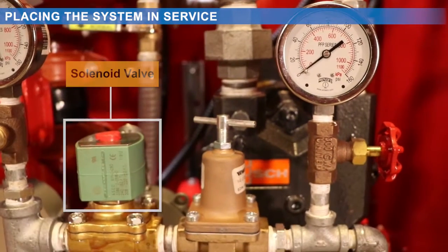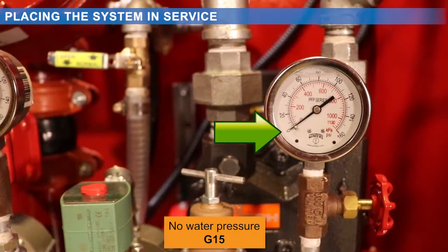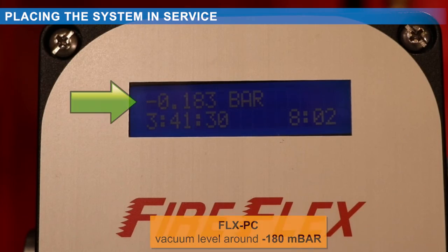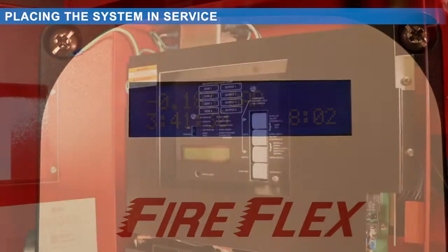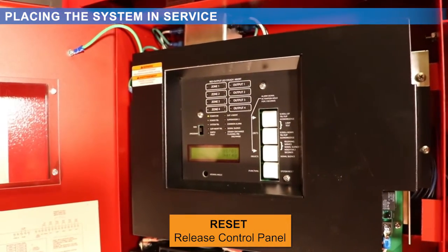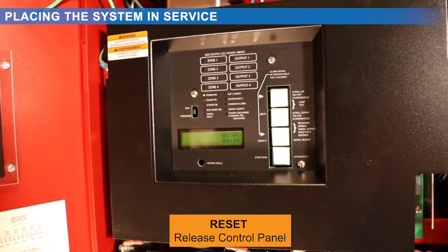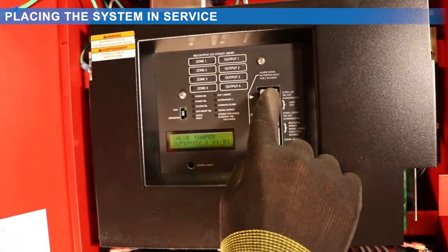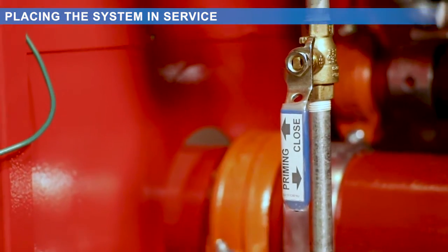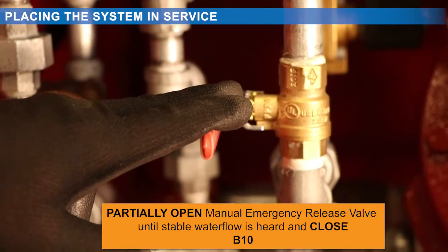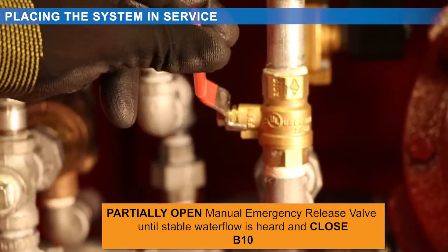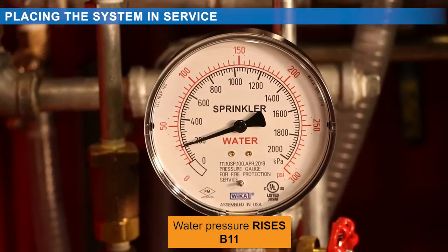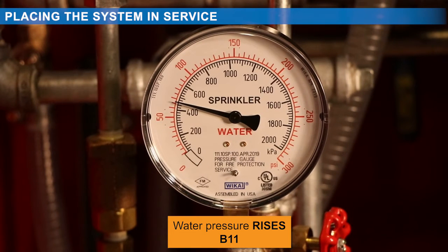When vacuum pump stops, solenoid valve should close. Gauge must now show no water pressure. FLX PC should display a vacuum level around negative 180 millibar. Reset the release control panel. Silence the alarm. Open the priming valve. To release any trapped air within the piping, partially open the manual emergency release valve until a stable water flow is heard and then close it. Water pressure slowly rises on the gauge. The priming pressure water gauge should now read the proper available water supply pressure.